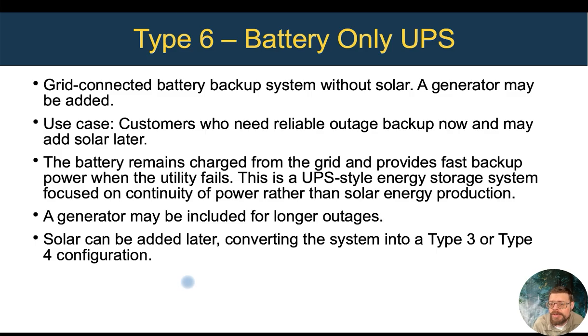But you do always have the option of adding a generator to the battery-based system. The way our inverter is set up, you're doing your UPS system, and it can just auto start that generator, run it for an hour, recharge the battery, then shut it back off. So you're using your generator, but you're also using it in a much more efficient manner instead of running it 24 hours a day to handle loads which are much lower than its rated output most of the time. Instead, run it fairly hard for an hour, recharge the batteries, and then go for another 10 hours on those, and run the generator for an hour. So a combination of the generator plus the battery can actually sometimes get you farther than just a generator alone would.